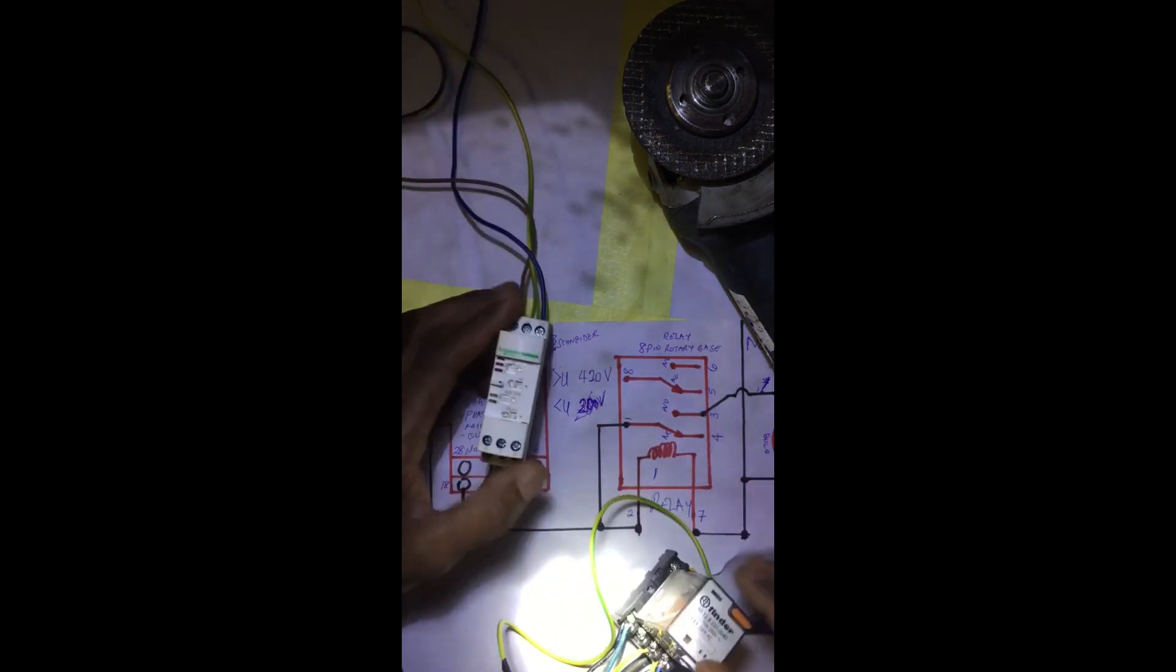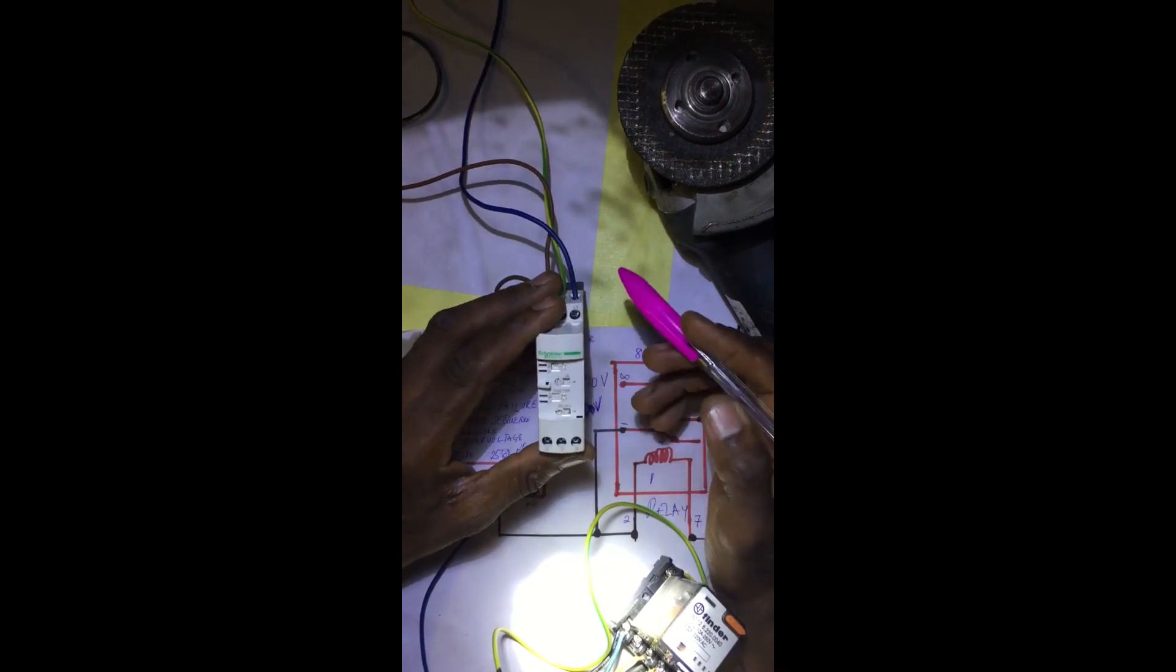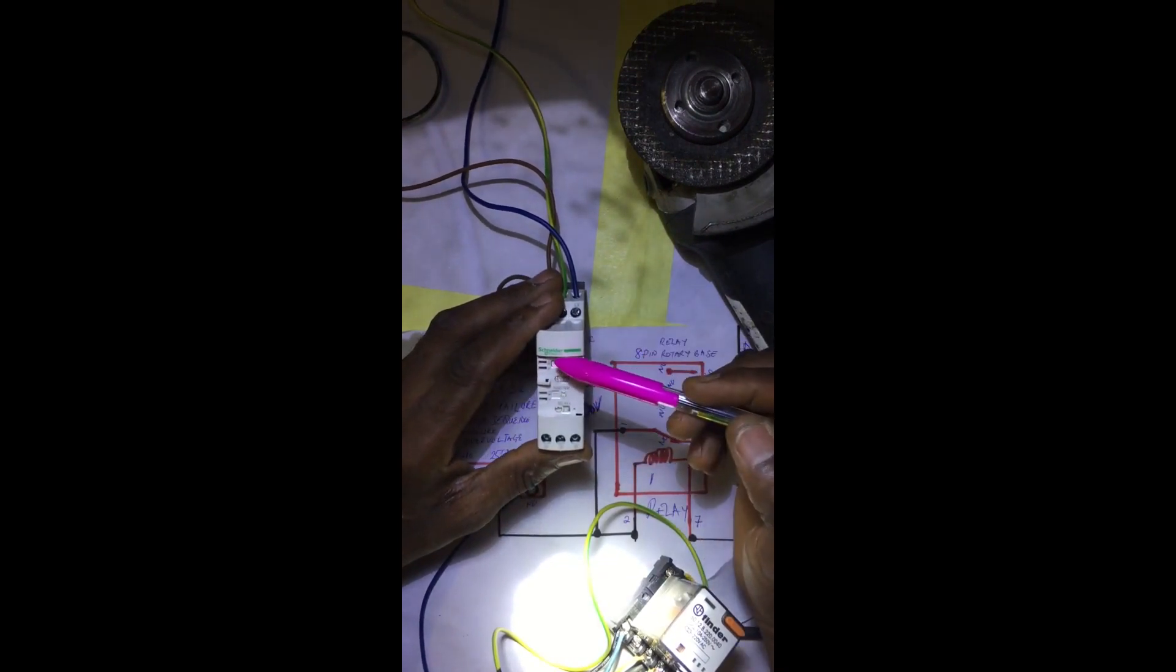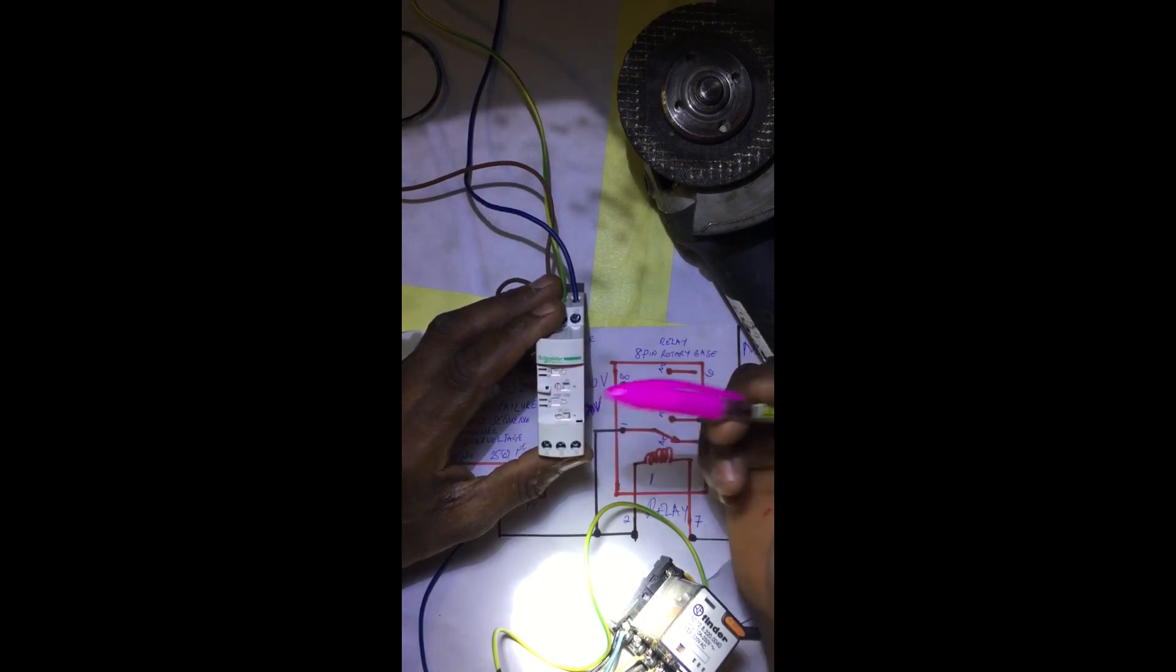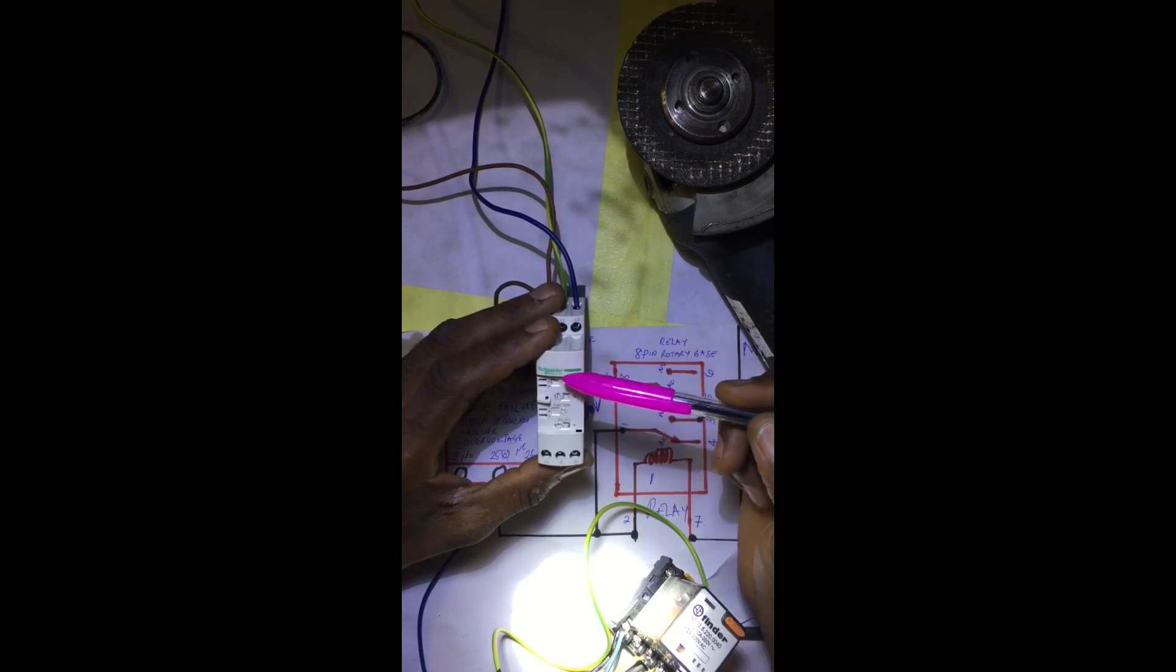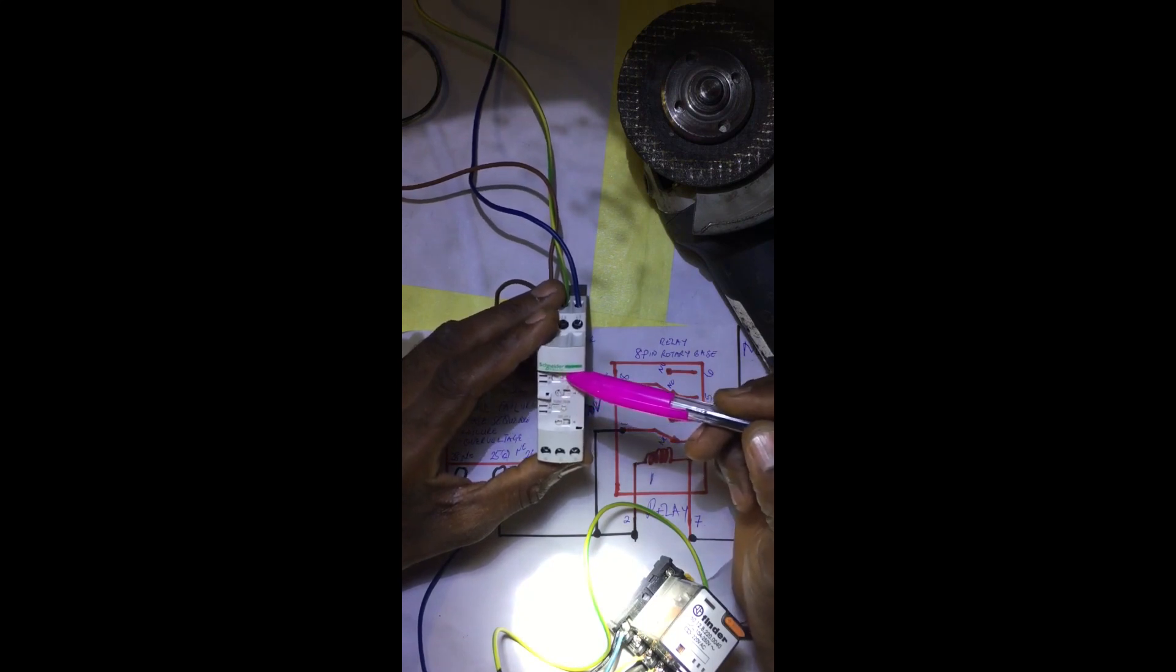So we are ready to roll. If you look at this relay now, you see that it has a greater-than dip switch that controls the upper threshold voltage and the lower threshold voltage. That means you are saying that this relay should conduct only when the voltage is between the lower threshold and the upper threshold voltage.